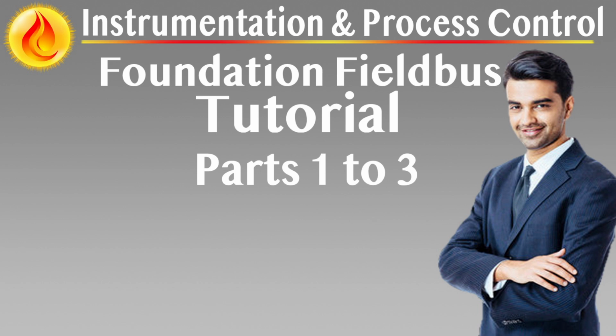Fieldbus is engineered for high reliability and diagnostic depth. Devices can continuously report status, fault conditions, calibration drift, and process abnormalities, enabling predictive maintenance strategies. This improves plant uptime, reduces manual inspection routines, and supports a proactive asset management approach. Diagnostic information is available at both the device and segment level and can be integrated with plant asset management software.